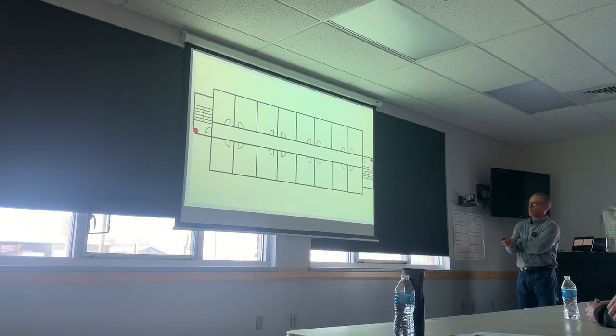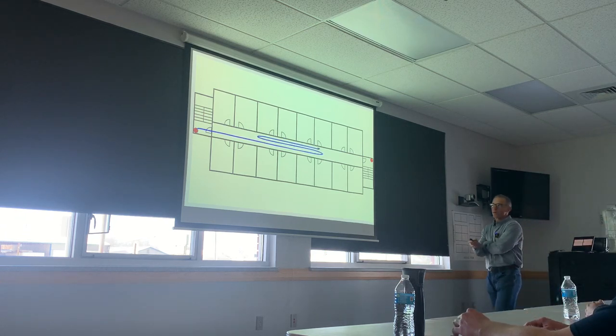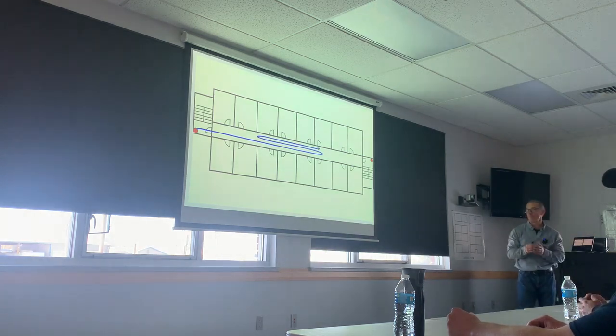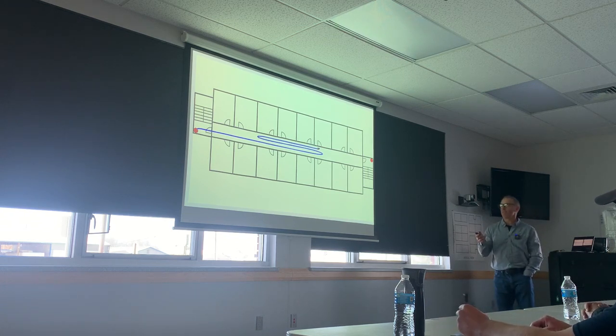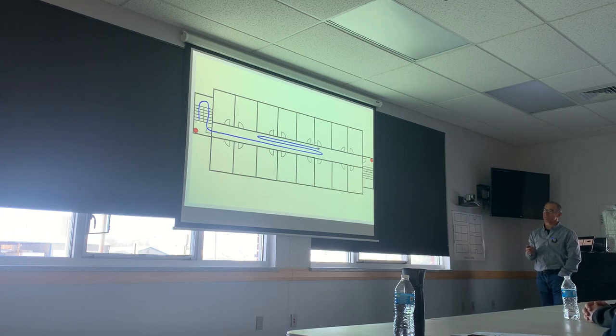Standpipes — you guys probably won't be dealing with a bunch of them. It might seem like it would be super quick, but I would not go to the standpipe. We don't use standpipes until we get to the fifth floor and above. A standpipe is essentially a black box where water goes in and you hope it comes out the other end — it's no guarantee. There can be debris, valves left open, and we've had workers cut out a section of pipe and never reported it.